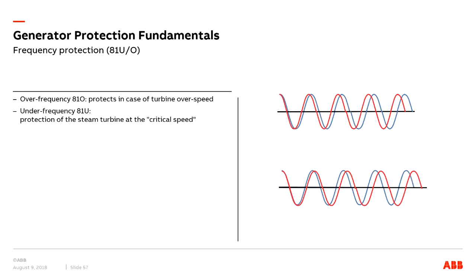Then we have the frequency protection. 81 over frequency protects in case of turbine over speed, and under frequency comes into play to protect the steam turbine at the critical speed situation.